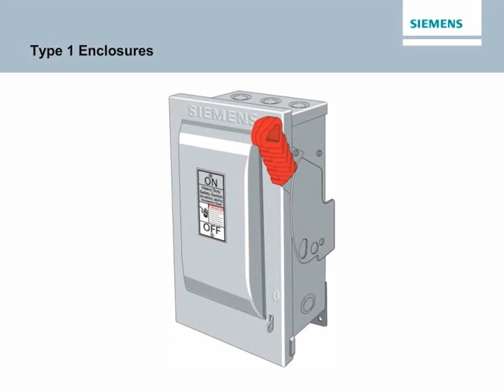Type 1 enclosures are intended for indoor use, primarily to provide protection against limited amounts of falling dirt and contact with the enclosed equipment in locations where unusual service conditions do not exist. Type 3R enclosures are intended for outdoor use, primarily to provide a degree of protection against falling rain and sleet. They are not intended to provide protection against conditions such as dust, internal condensation, or internal icing.